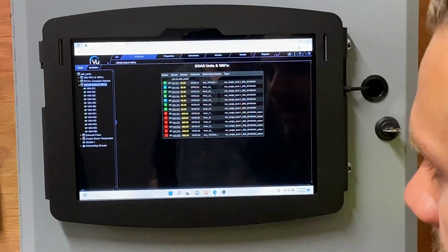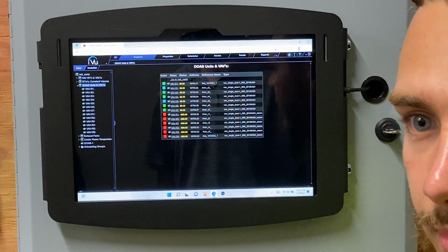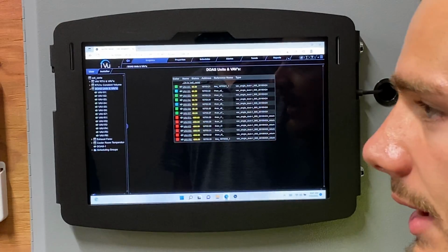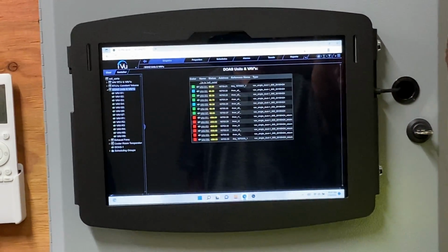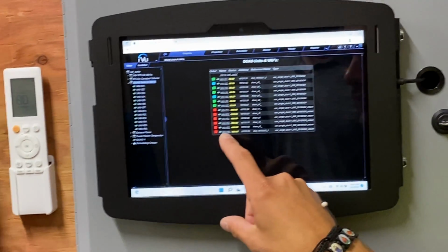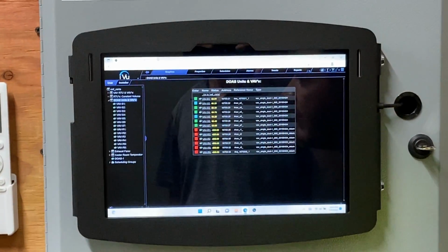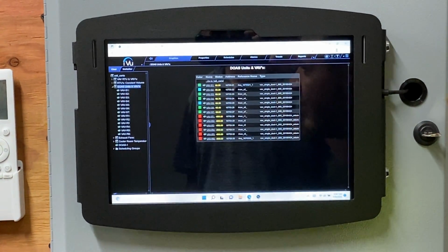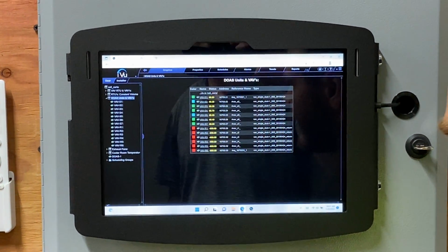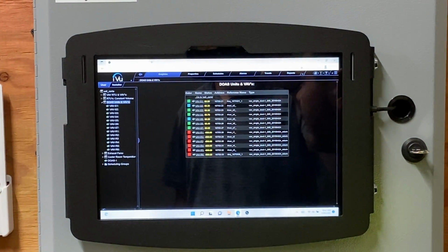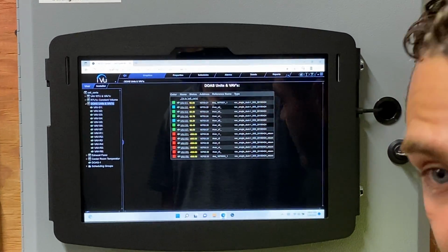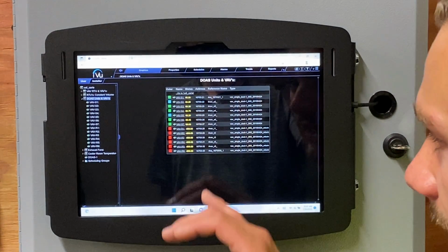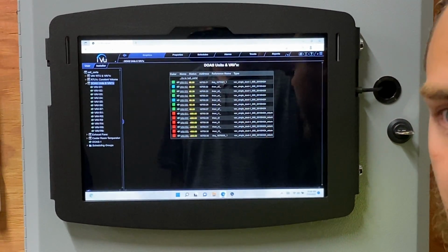So when you're looking at this and see all red boxes, that's a huge problem - we're not reading values. You'll see it says VAVR for the return, so it differentiates between them. That color is only concerned with temperature, it doesn't care about anything else - it's not going to tell you if something's not operational, it's just concerned with temperature.